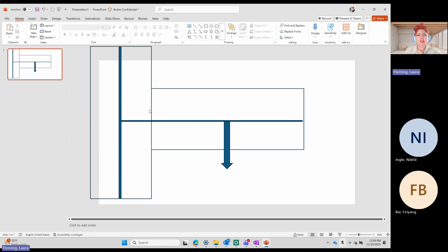Yeah, so calibration, system calibrations, and then it's where we do our indentation axis calibration. That same screen with all the transducer constants listed. Okay. And there should be constants for the scratch calibration, load scale factor and displacement scale factor. Do you see that? Yes. Okay, is there an imaging position listed? Imaging position. Yes. Okay, what is it? Minus 9.1. Minus 9 what? Sorry? Minus 9.9. Oh, you're sharing. Sorry. Got it. Okay. Can we call it 10 for the purposes of training as I'm explaining this? Sure. Thanks. I just wanted it to be relatively close to yours so that you could understand what was happening.